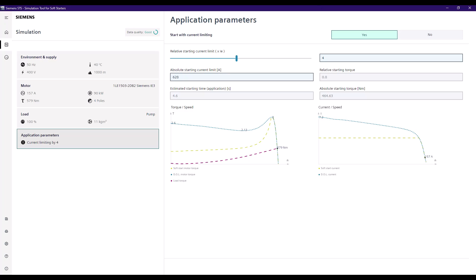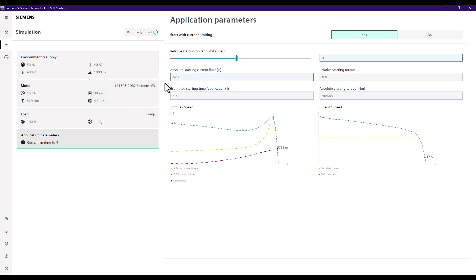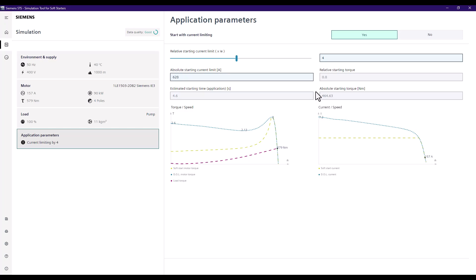In the application parameters we define how we want the soft starter to start the motor — typically with current limiting or without. By default it always starts with current limiting, and the default value is four times the rated current of the motor. We've got 157 amps on our motor in this case, which automatically populates the absolute starting current limit value of 628 amps. This also calculates the estimated starting time and starting torque for the application.